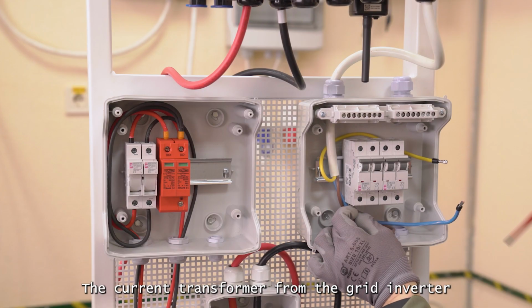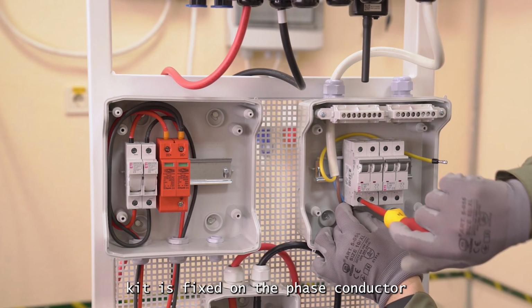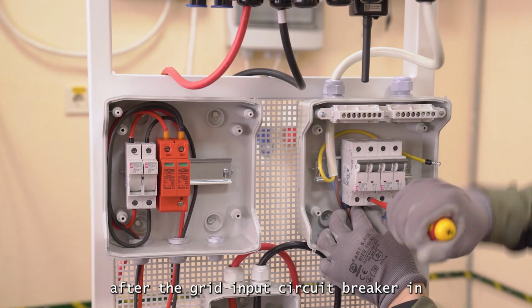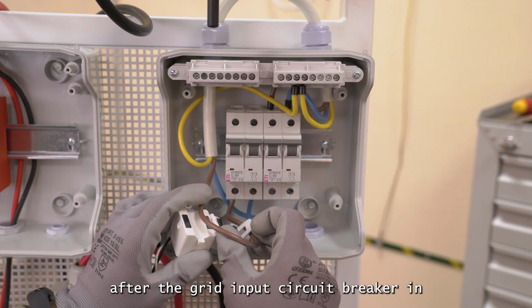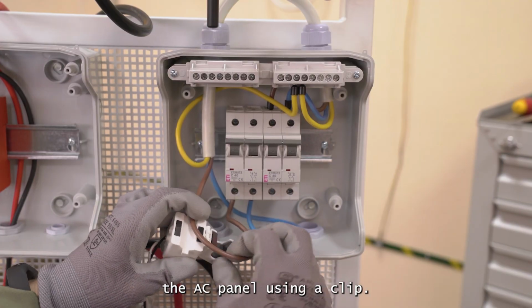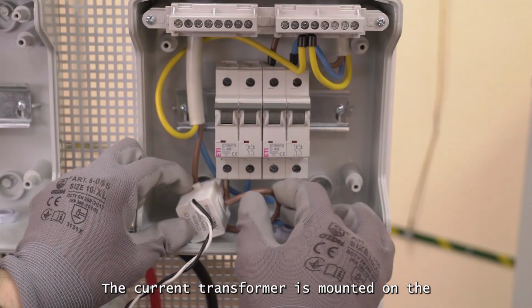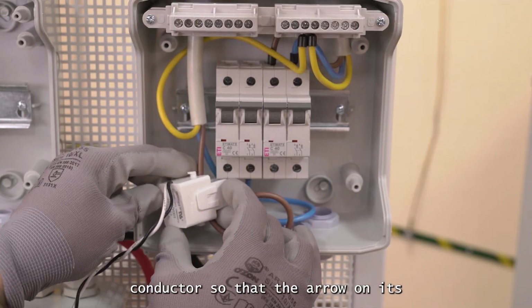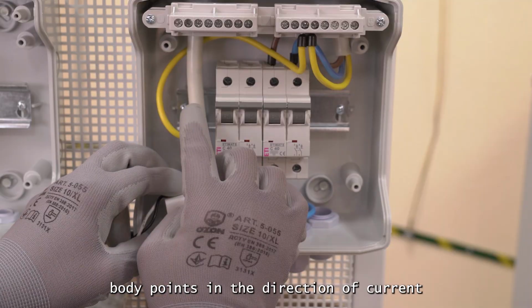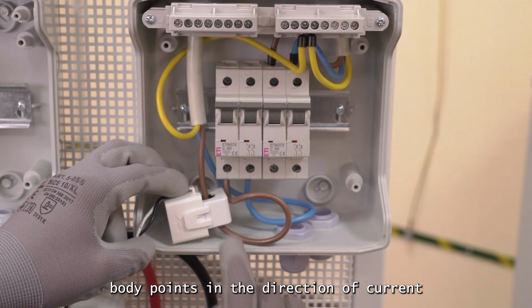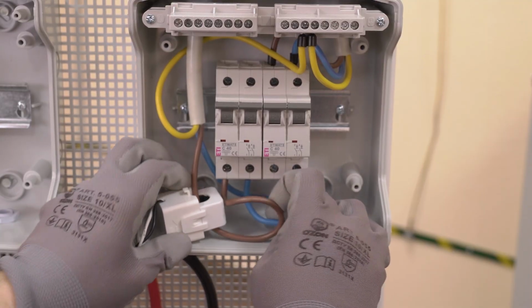The current transformer from the grid inverter kit is fixed on the phase conductor after the grid input circuit breaker in the AC panel using a clip. The current transformer is mounted on the conductor so that the arrow on its body points in the direction of current flow to the inverter.